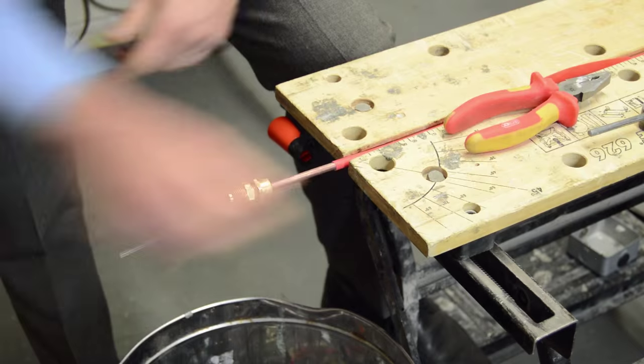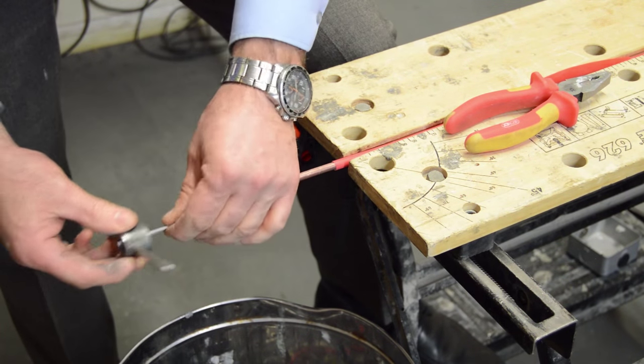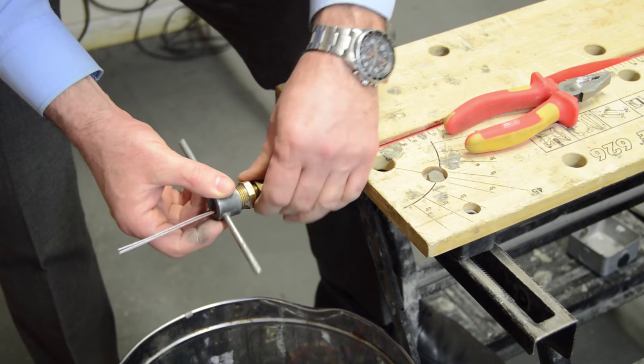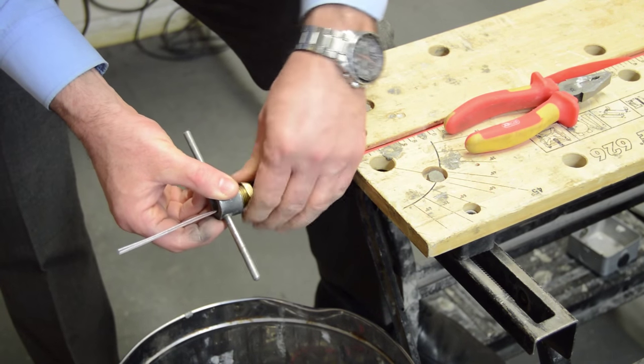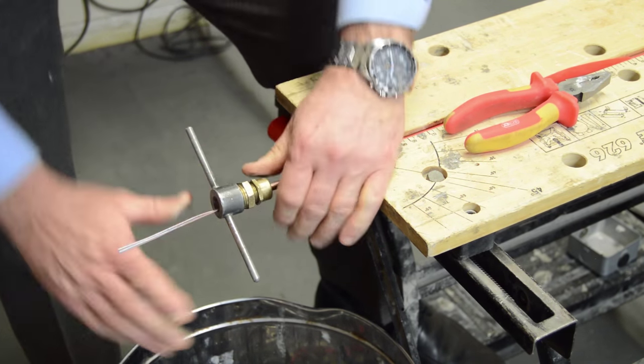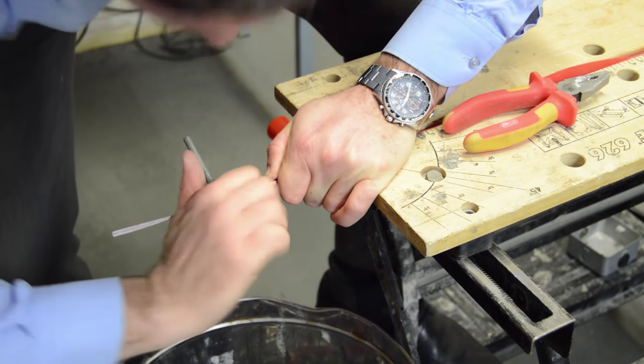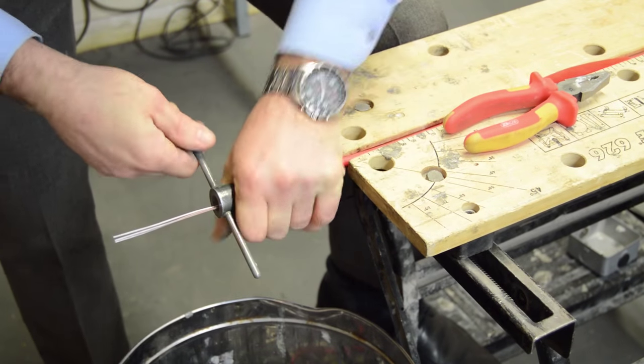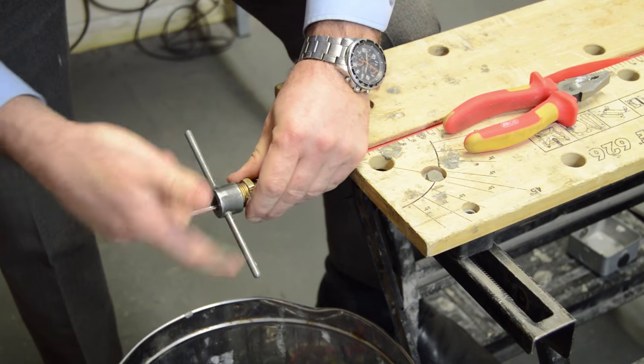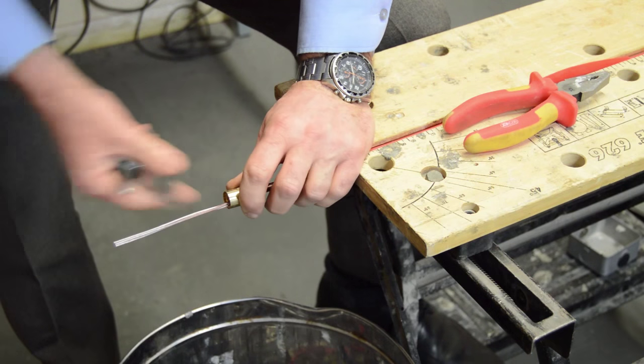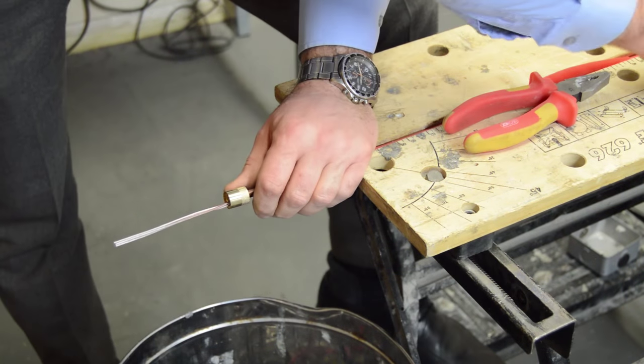There is other methods to put the pots on for people who don't like the pliers. The first one is the potting tool. This one goes over the top and gets tightened onto the brass gland. And then we wind the pot on using the potting tool. The reason I don't like using the potting tool is you can't see how far you've wound the pot on easily.